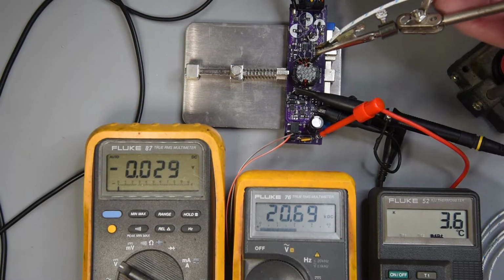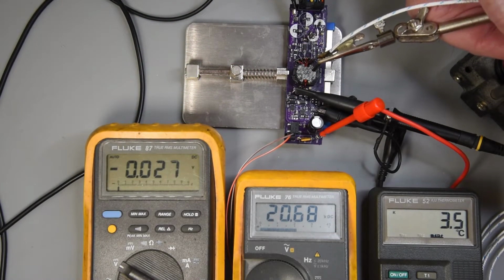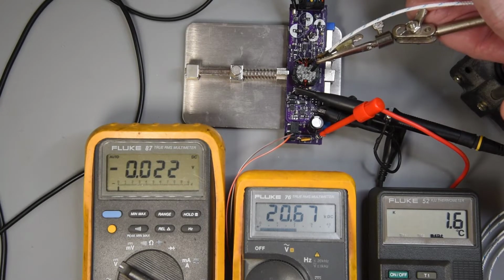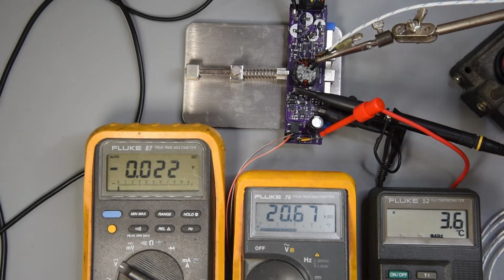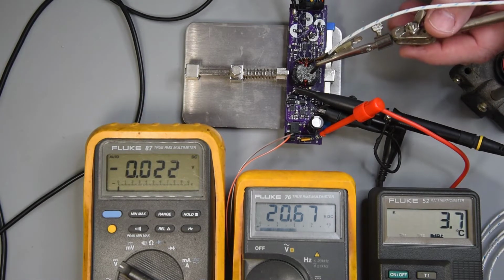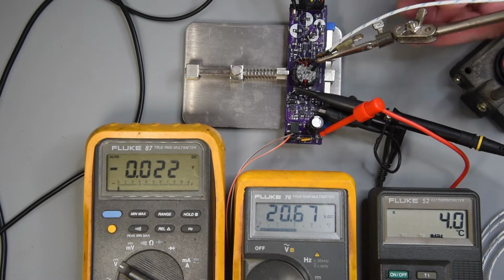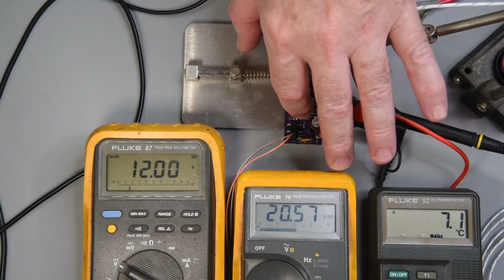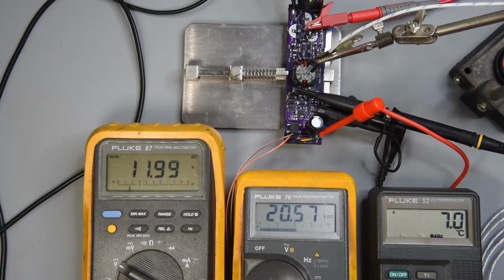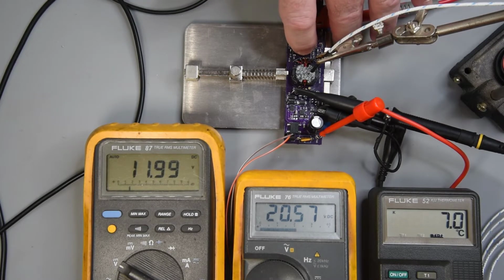I do want to check the temperature rise of the transformer. This one feels cooler to the touch than the last one. There is a bit of air moving in the room, so it will read a bit lower than the still air reading would be. I've got about a 6.7 watt load on it, so about maximum for what the design was. Around a 7 degree centigrade rise, that's not bad. The controller feels cooler than the transformer. It feels like the output rectifier may be the warmest part.